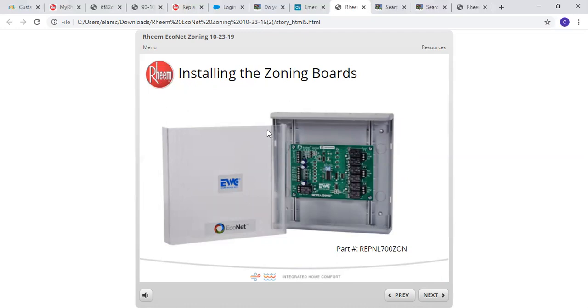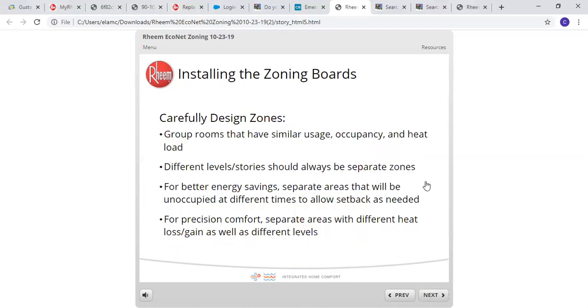Installing the zone boards. When you order the zone kit, you get this nice little clear cover and a nice box to mount it in. And this is the REP NL 700 ZON board. It is best to carefully design your zones, grouping rooms that have similar usage, occupancy, and heat load. Different levels, stories should always be separate. For better energy savings, separate the areas that will be unoccupied at different times to allow setback as needed. And for precision comfort, separate areas with different heat loss and gain as well as different levels. Typically, unless you're starting from scratch, you're going to be stuck with the ductwork that you have, and you just try to separate it accordingly. Usually like a basement, main floor, upper floor.